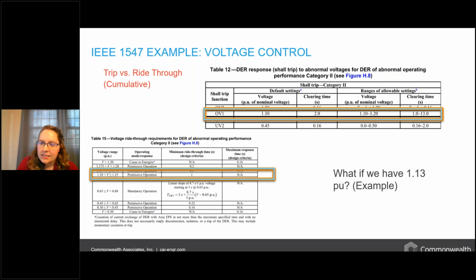And there's a recommended default value saying that around 1.1 or 110%, if we're going to de-energize part of our system, we'd have to do that in 2 seconds. But continuing to the right of the chart, we see there's actually a range of allowable values and a range of clearing time that we as the operators could have influence on.